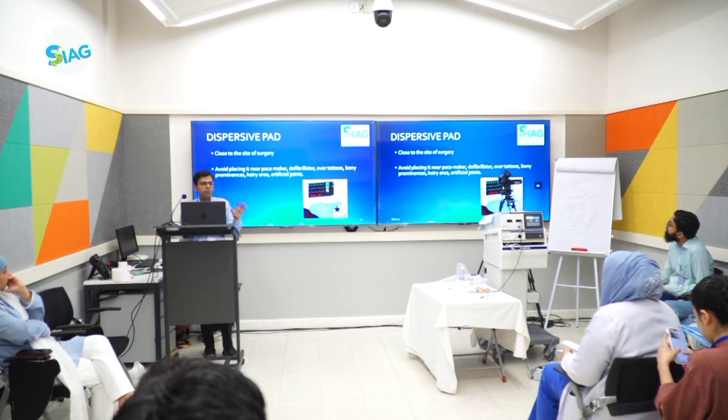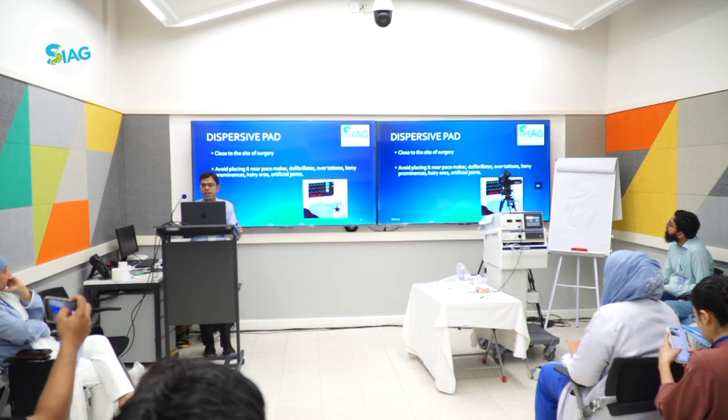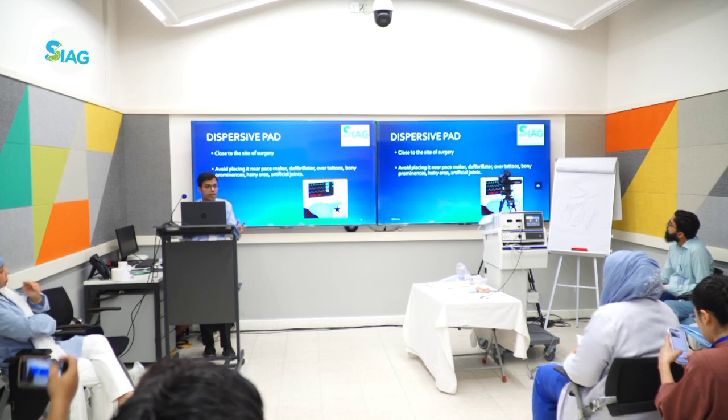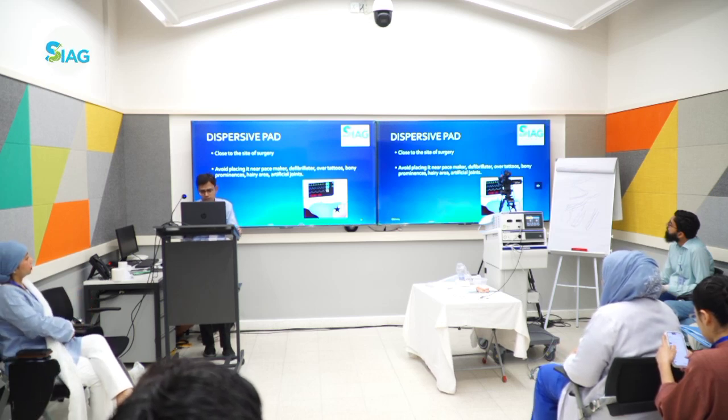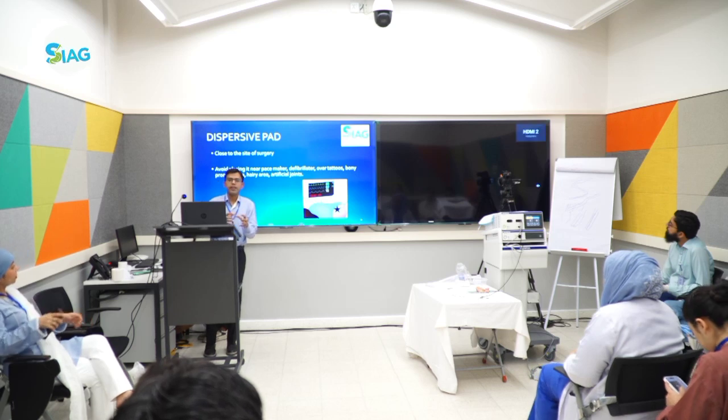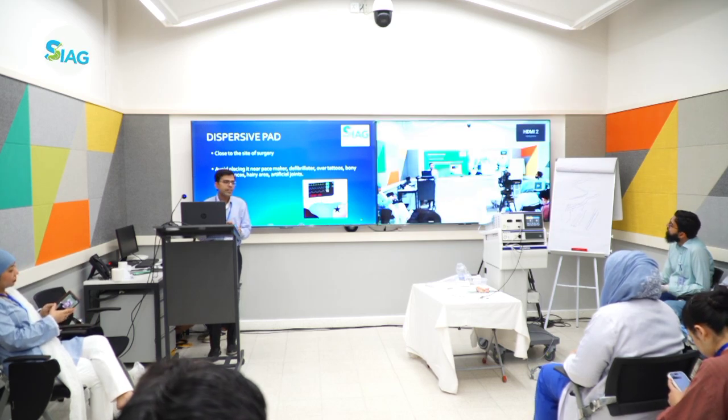So avoid placing it near a pacemaker, very important, defibrillator, over tattoos, bony prominences, hairy areas, and artificial joints. There should be a good contact. This is very important. Otherwise, this might lead to skin burn.